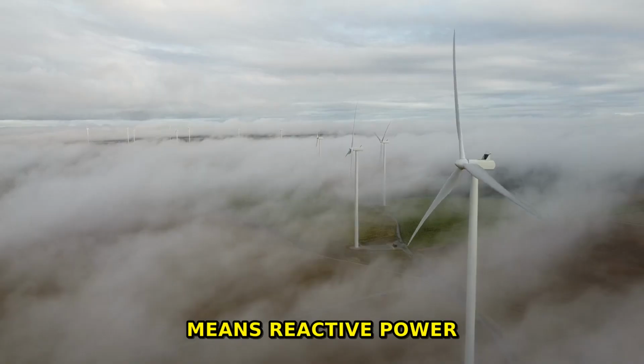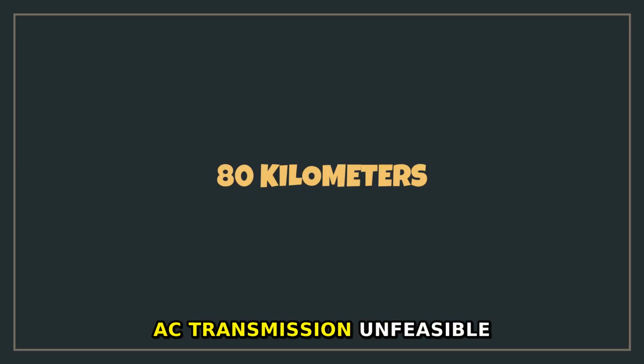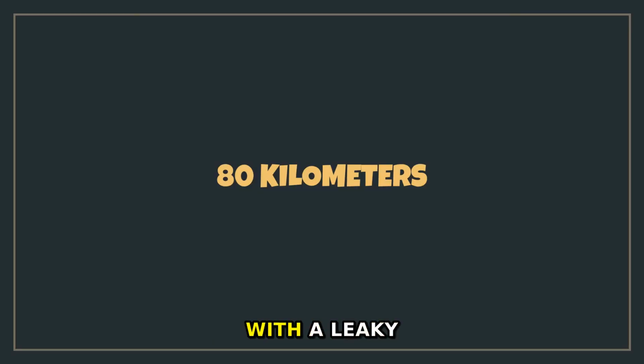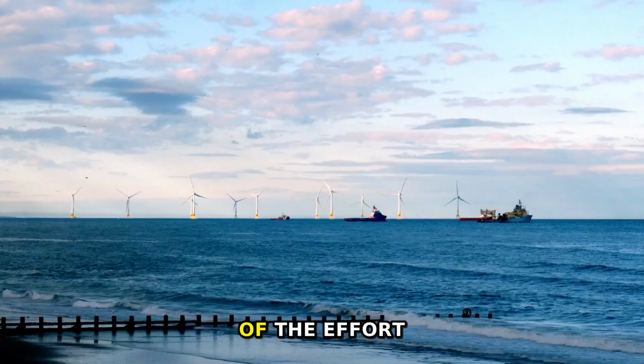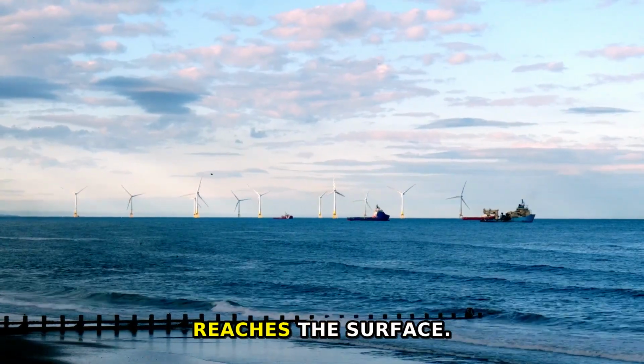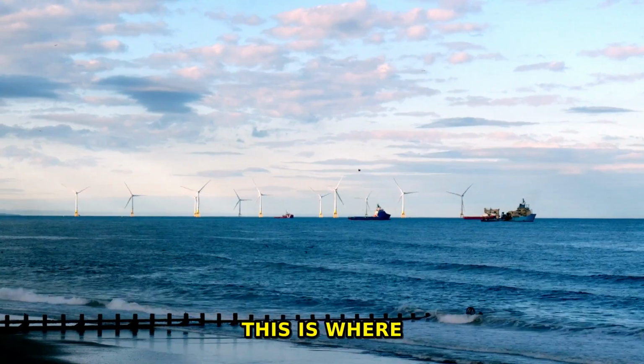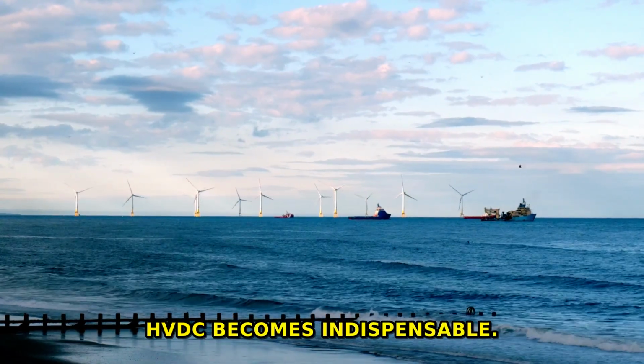This means reactive power losses in AC subsea cables are enormous, making AC transmission unfeasible for distances beyond roughly 50 to 80 kilometers. It's like trying to fill a bucket with a leaky hose underwater, most of the effort is lost before the water even reaches the surface. This is where HVDC becomes indispensable.